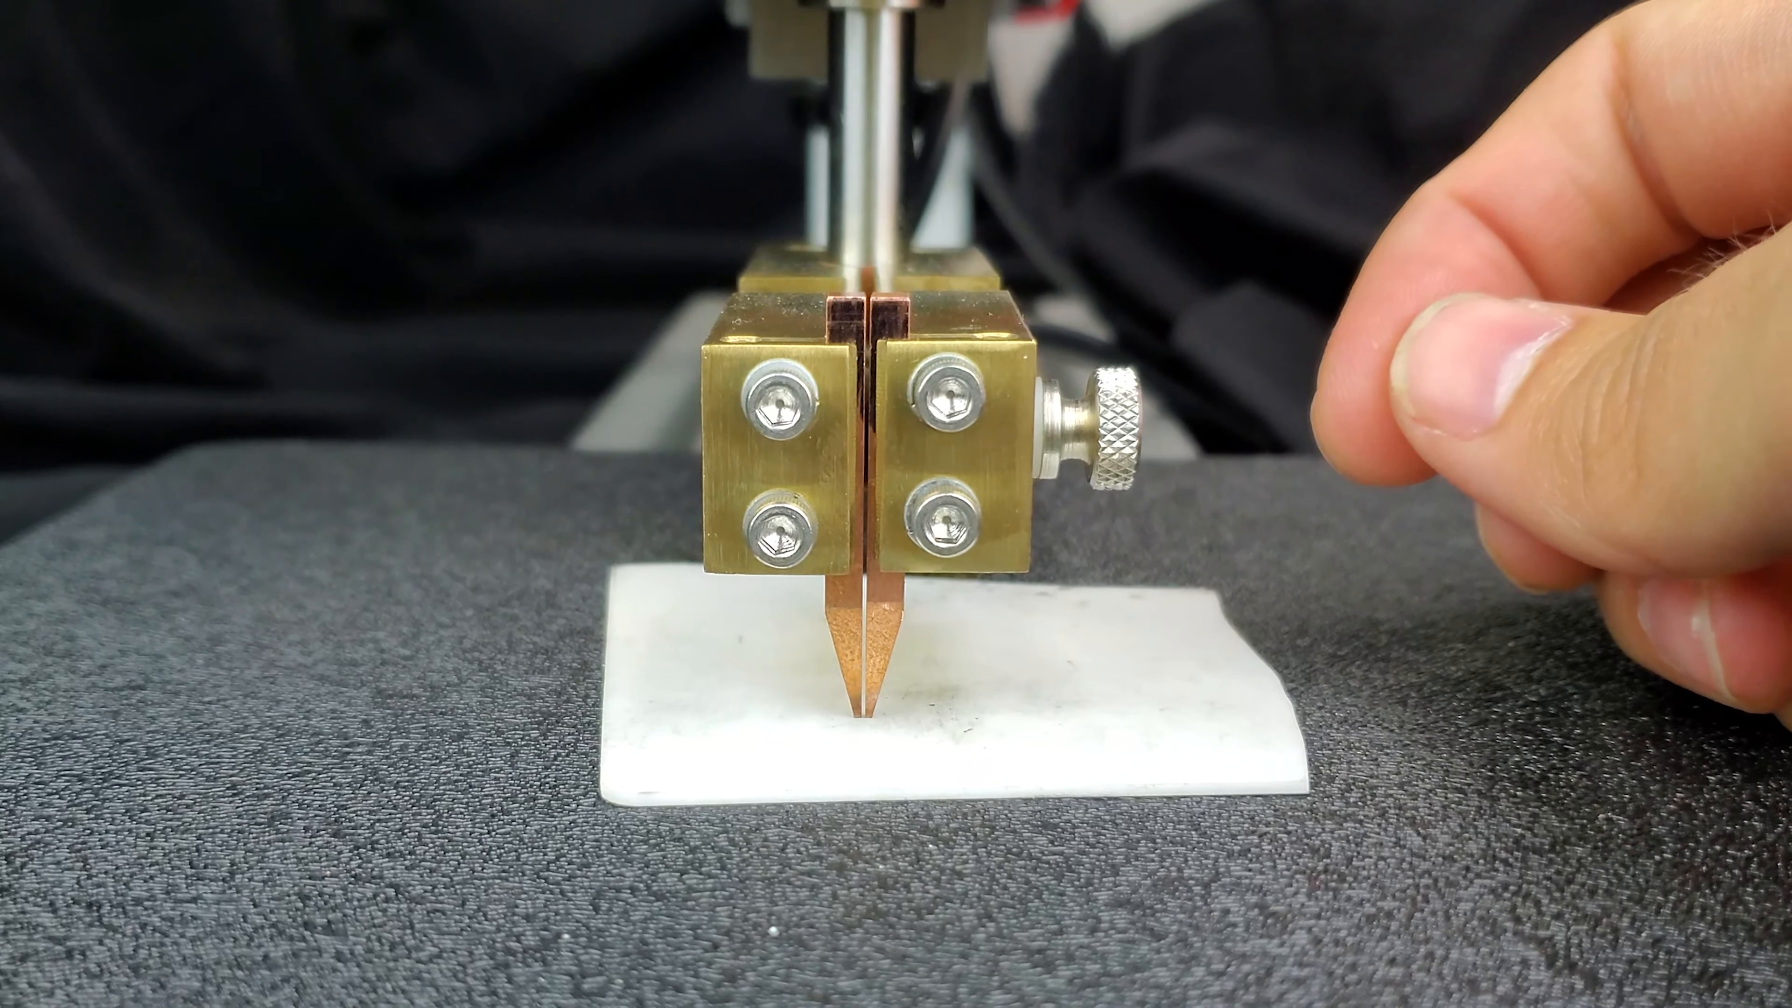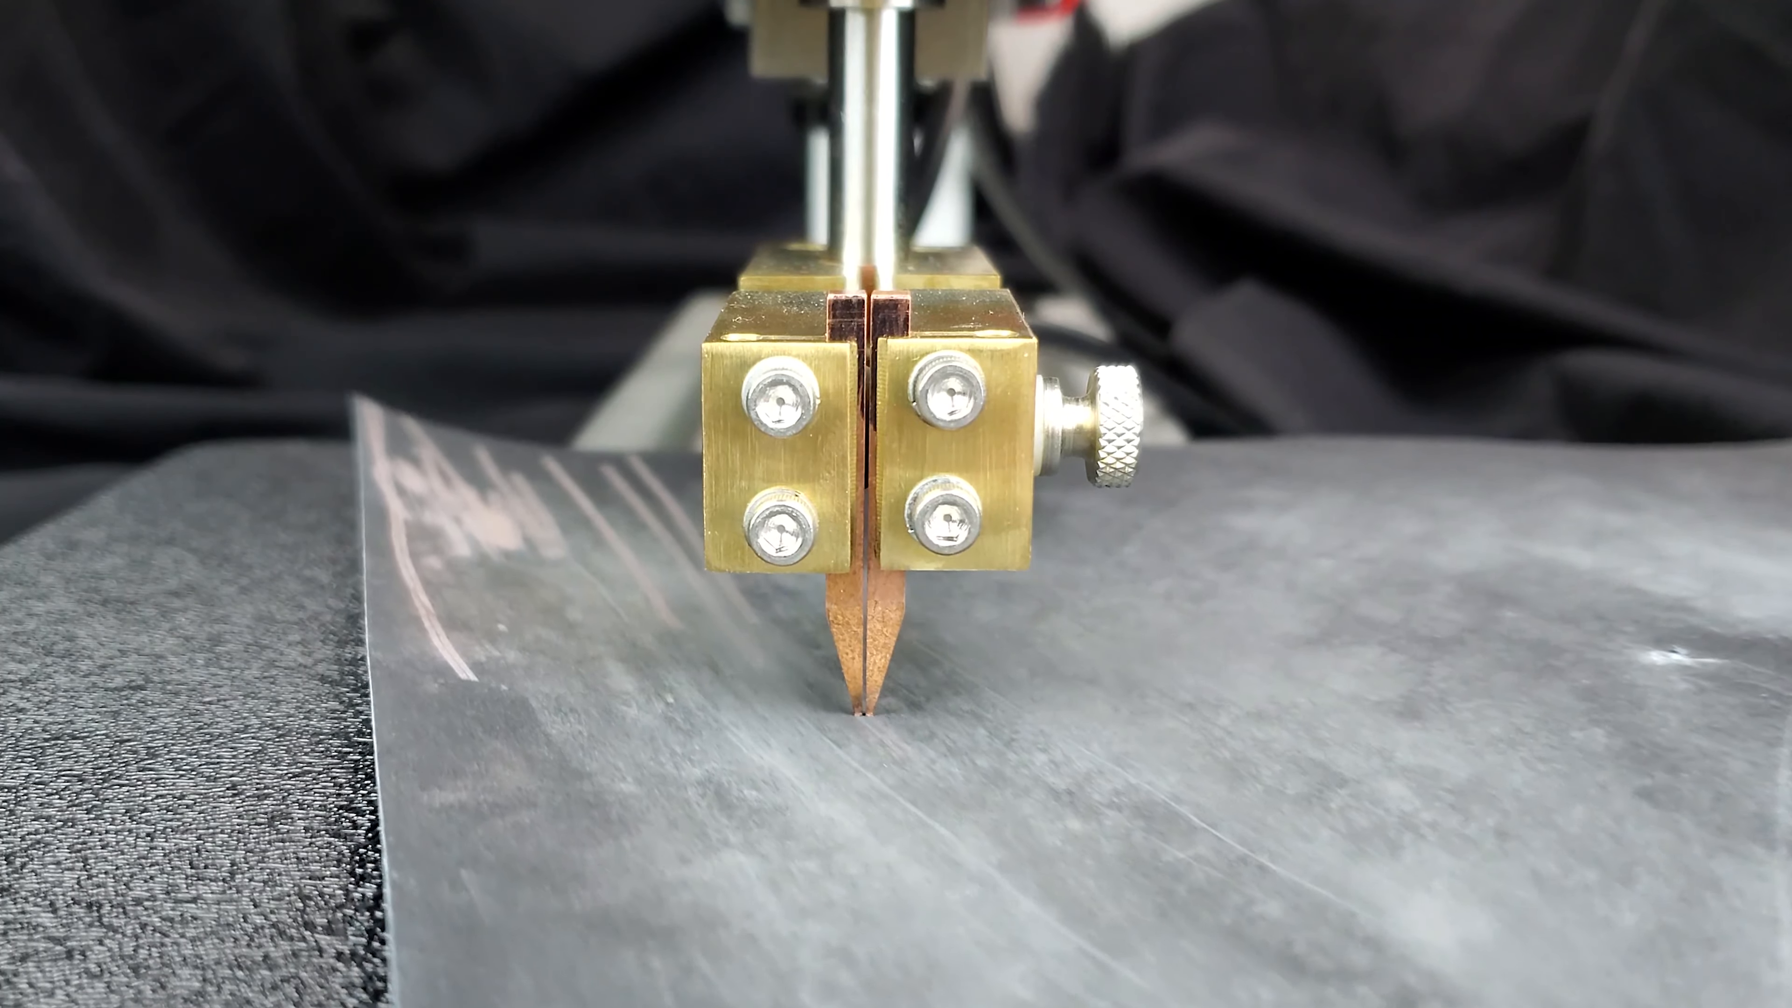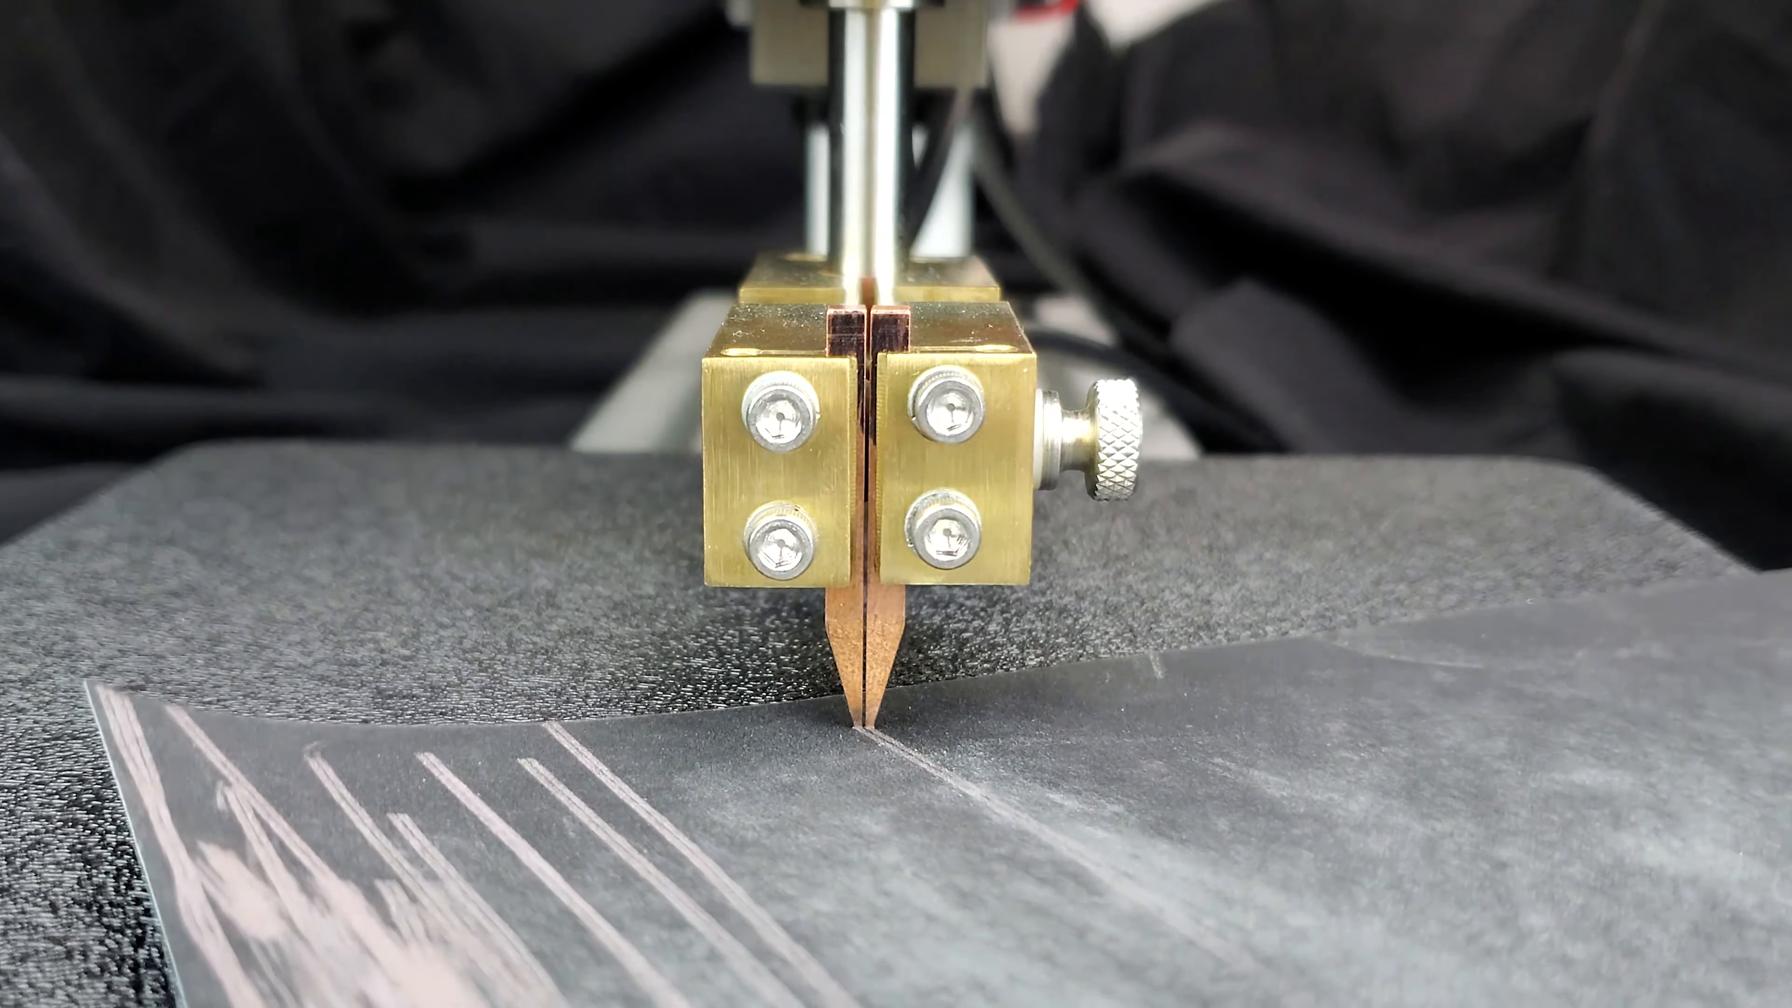Again, checking our work distance. And then, in order to maintain our electrodes so they both come down on the part evenly, we get some fine grit sandpaper. I'm using 600 here. I'm going to drag it across the electrodes.